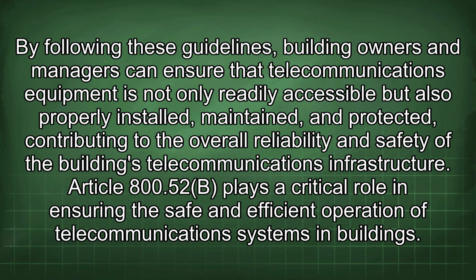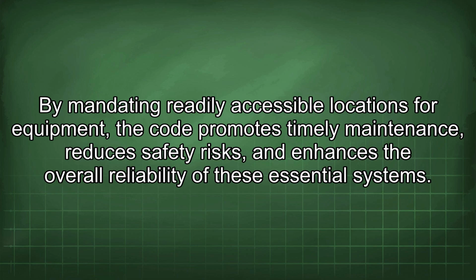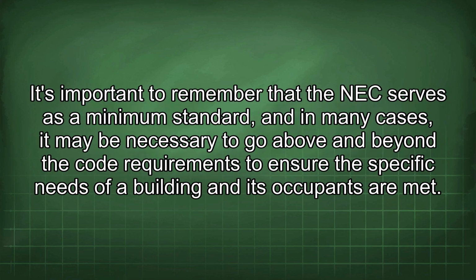Article 800.52b plays a critical role in ensuring the safe and efficient operation of telecommunications systems in buildings. By mandating readily accessible locations for equipment, the Code promotes timely maintenance, reduces safety risks, and enhances the overall reliability of these essential systems. It's important to remember that the NEC serves as a minimum standard, and in many cases, it may be necessary to go above and beyond the Code requirements to ensure the specific needs of a building and its occupants are met.